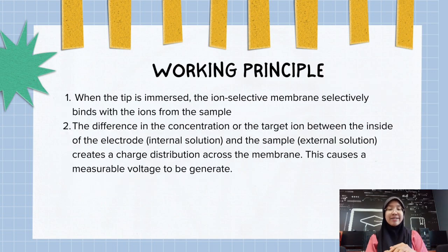Next, let's go to the working principle. When the tip is immersed inside the solution, the ion-selective membrane selectively binds with the ion from the sample solution. Thus, the difference in the concentration of the target ion between the inside of the electrode, which is the internal solution, and the sample, which is the external solution, creates a charge distribution across the membrane. This causes a measurable voltage to be generated.